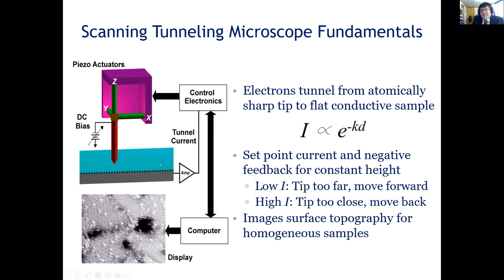It's colored black and white. White is high, black is low, because it's a topographic image. It doesn't capture color information like a traditional microscope would. So it acquires the image in a raster scan because it's a scanning probe. It has to take the images one pixel at a time. So it does that in a pretty straightforward method. It has to go over every pixel.